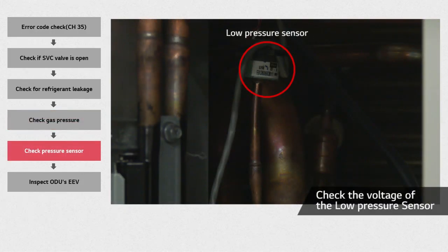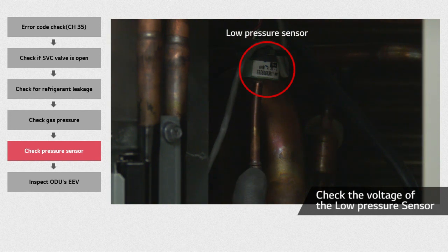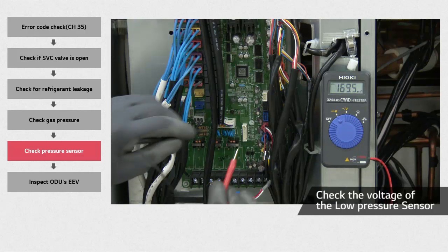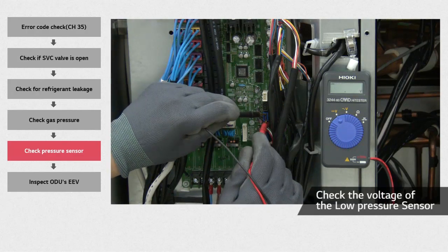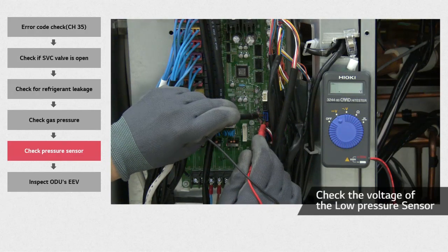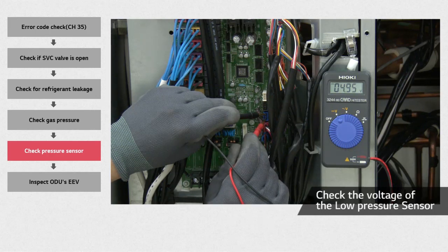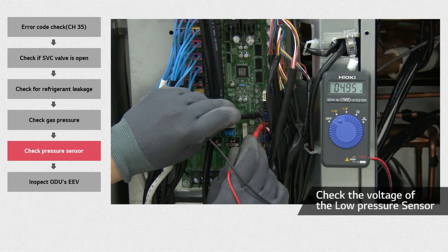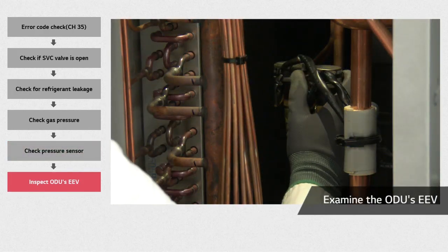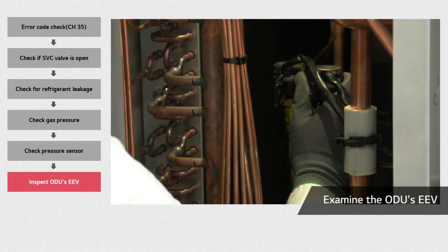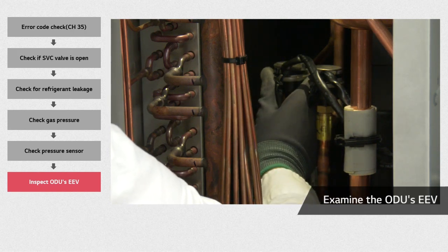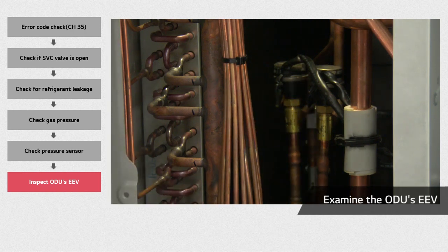Locate the low pressure sensor — it is shown in the image with the white label. Measure the voltage coming from the PCB pressure sensor, then check if the measurement is 5 volts for the blue low pressure connector in the external PCB. Finally, check the outdoor unit electronic expansion valve. When you reset the PCB power, the EEV opens and closes again. You can also feel it vibrating in your hand.